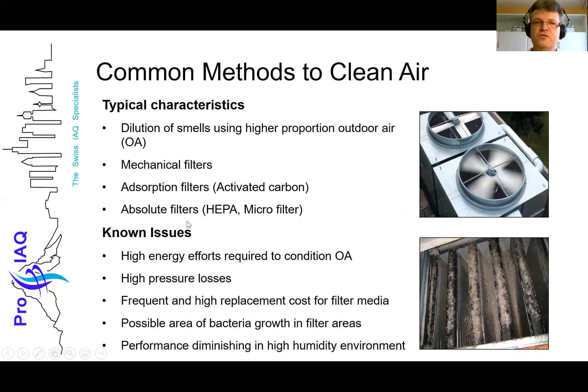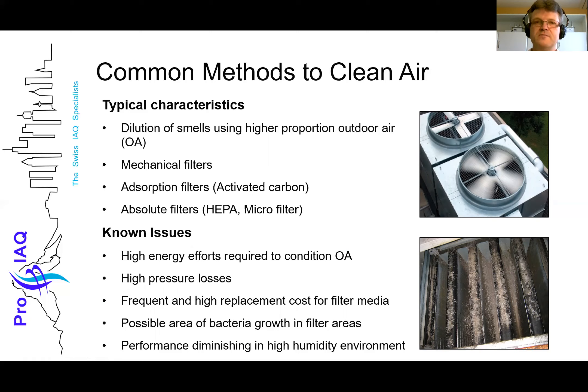The issue with these filters is the high energy effort required to condition the outdoor air. If we bring in fresh air, we normally have to cool it and dehumidify it. We have high pressure losses through these filters, high replacement costs, areas of bacterial growth, and low performance when humidity is high. In the Middle East during summer, the humidity is always very high when we have to cool down the air.